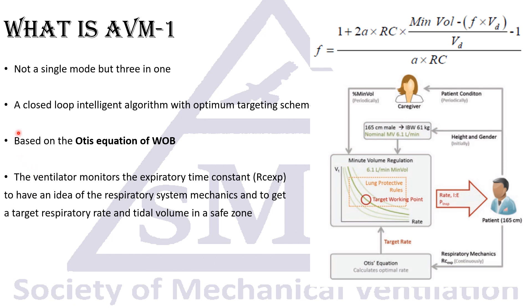AVM1 is not a single mode but almost like three in one. When the patient is passive with no effort, the ventilator acts as a pressure control mode. If the patient is active but not fulfilling the whole target respiratory rate, the mode almost becomes intermittent mandatory ventilation. And if the patient is targeting all the breaths, it becomes almost like a pressure support ventilator. So again, it's not a single mode — it's a closed loop intelligent algorithm with an optimum targeting scheme.